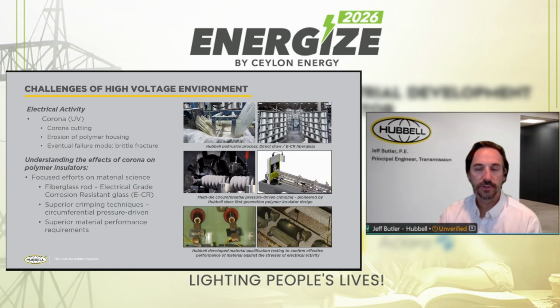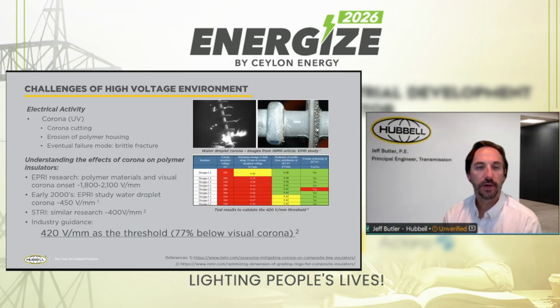So it led to some greater focus on some of the challenges that these insulators face in order to extend the life of these insulators. One of those outcomes as well was the understanding of corona and corona activity, and that's referring to visual and audible corona. And so EPRI, together with STRI, provided a recommendation on a voltage gradient.